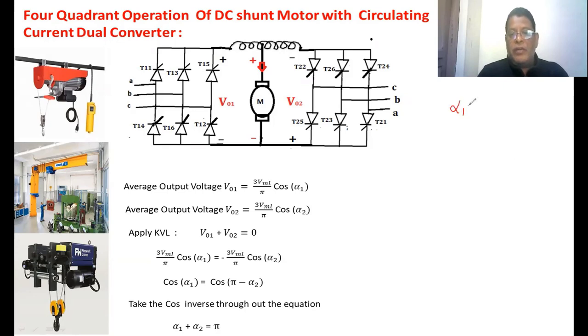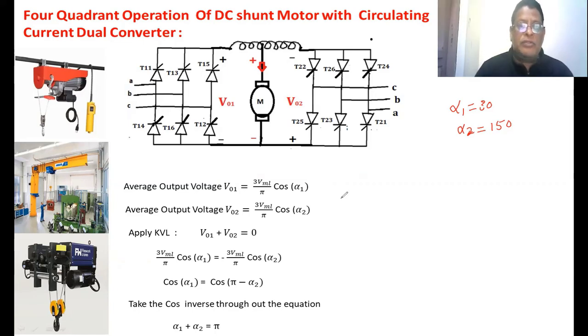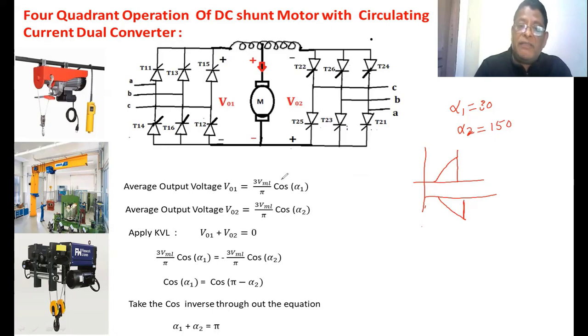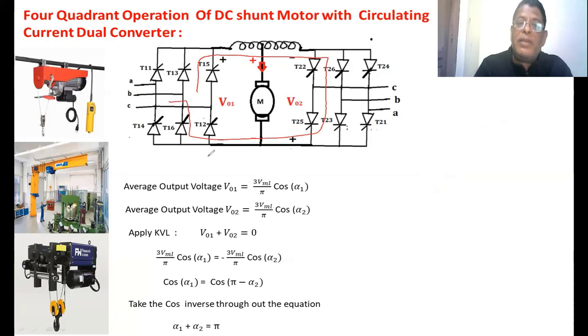For example, if alpha 1 = 30°, then alpha 2 = 180° − 30° = 150°. Converter 1 operates as a rectifier while Converter 2 operates as an inverter. Circulating current flows because, even though the average output voltages of the two converters are equal, there is a difference in their instantaneous voltages. Due to this instantaneous voltage difference, a circulating current flows between the converters. Since the path resistance is very low, this current can be high, so an inductor is used to limit it.